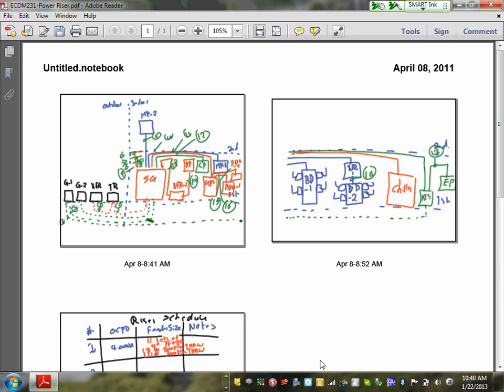We might be at 100K or 125K on that gear, which makes this way more expensive. So there are some more differences, right? If you go open transition, you probably could get away with 65K because the two gens tied together is less than 65, and the utility's probably 65. And when we do a fault current study, we always assume worst case that the fault could occur when everything's connected together. Plus, you have to figure in all the motor loads over here feeding into that fault. So it's just some things to think about: open, closed, derived new, bonded, unbonded, all the things that affect the system.